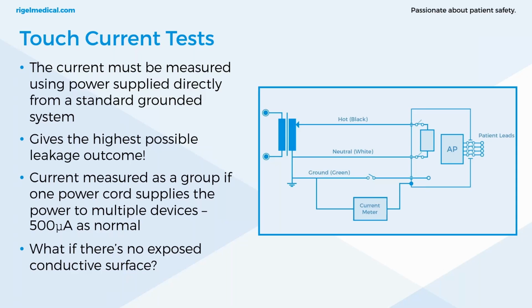For obvious reasons, that adapter also must be removed from the measurement once it's completed. So you're only using that adapter for testing purposes. It's obviously a hazard and needs to be carried out by someone that knows what they're doing. But it's a good suggestion in NFPA 99 for those isolated systems that we quite often come across in healthcare facilities.